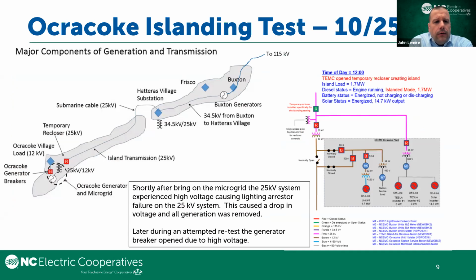You can see, as I talked about, where we go 115,000 volts through the Outer Banks region and then transition to the submarine cable. And you can see the location of our diesel. We have that installed on the 12 kV system along with the load. Well, initially when we installed the battery component of the microgrid, we put it on the 25 kV side. And we went through our use cases and we said, we want to test islanding and test the ability during non-peak times to serve the island with the microgrid.